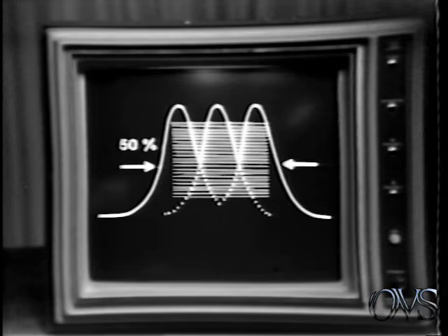Because the human eye sees this much of a spot, it cannot accurately discern where the 50% points are. If, however, several lines are merged, their intensity graphs begin to overlap. As these lines are merged closer and closer, the point where they can just be distinguished from each other with the eye is the 50% point on the algebraic sum of their intensity graphs.